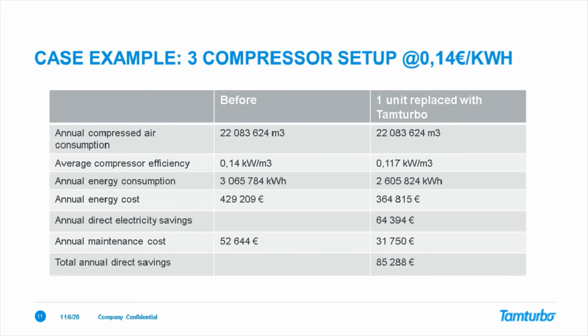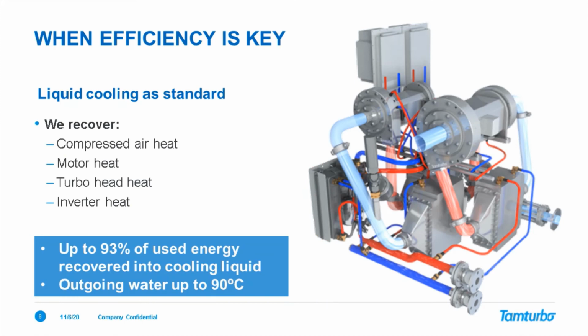All right, then there's a question about contaminants. How high is the possibility of cooling water contaminating the compressed air during the cooling process? Okay, the cooling water is not in contact with the air. Let me dig that picture up. It's only on the heat exchangers, on the other side of the wall to the air, and also for the turbo heads, it doesn't get in contact with the compressed air.